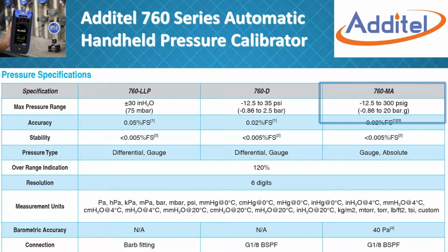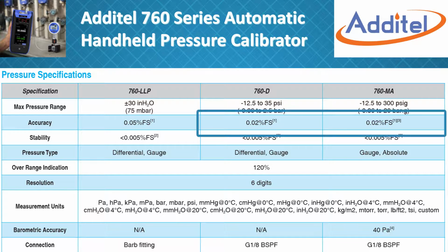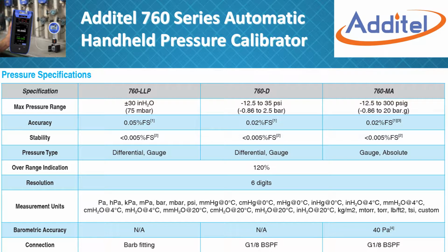So the accuracy for the 2 higher range products is 0.02% full scale. That's of whichever module is included inside the base. So you always get a module that matches the full scale range of each one of those different units. So if you buy the 760-MA, you get a 300 psi module in there, and then you can buy other modules to install internally if you need better accuracy in lower parts of the range. So 0.02% full scale for the 760D and the 760MA. The LLP, the low pressure one, is 0.05% of full scale.